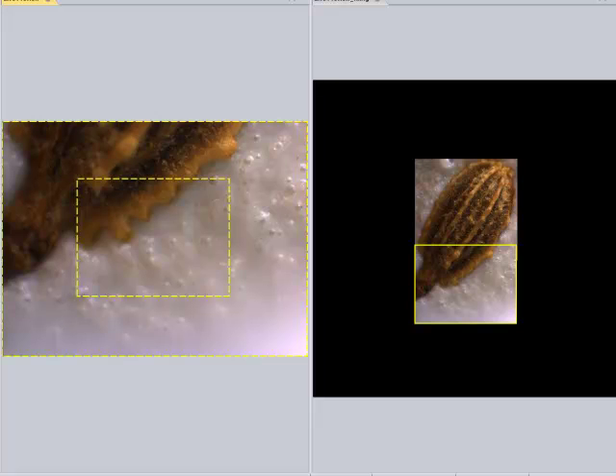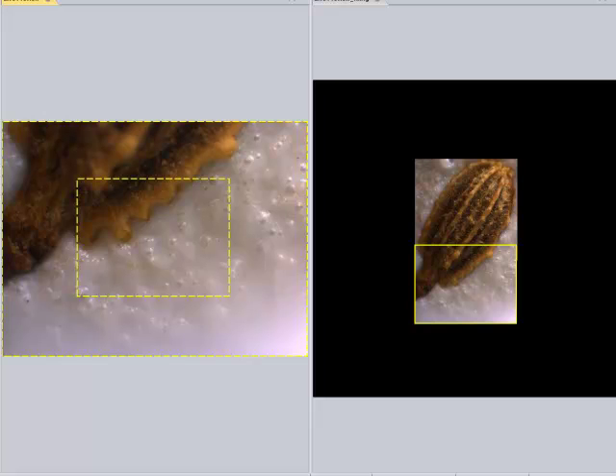EDF is something that if you feel like you've missed a spot, if you focus too quickly by a region, because there's a huge amount of processing going on, the frame rate is reduced, and you need to go a little bit more slowly than you do when you're typically moving focus or a stage around. That looks pretty good.